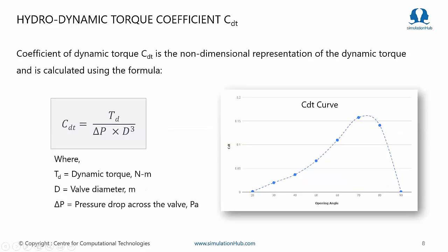Here I am introducing the coefficient of hydrodynamic torque, popularly known as CDT. This is the non-dimensional representation of the dynamic torque, calculated using a formula that includes the dynamic torque itself, the valve diameter, and the pressure drop across the valve. When CDT is calculated for each angle of opening and plotted across the full valve operation range, it gives a typical CDT curve for a butterfly valve.